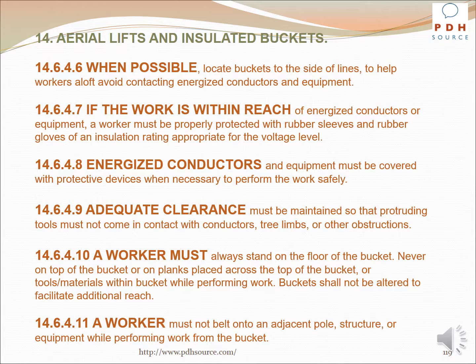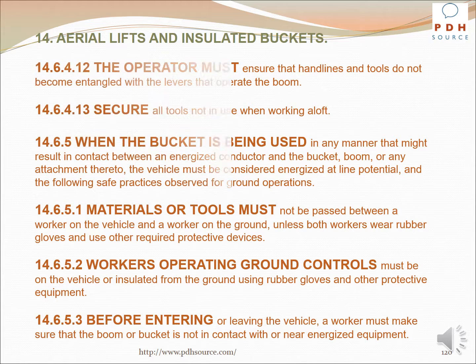Adequate clearance must be maintained so that protruding tools must not come in contact with conductors, tree limbs, or other obstructions. A worker must always stand on the floor of the bucket, never on top of the bucket or on planks placed across the top of the bucket or materials within the bucket while performing work. Buckets shall not be altered to facilitate additional reach. A worker must not belt onto an adjacent pole, structure, or equipment while performing work from the bucket. The operator must ensure that hand lines and tools do not become entangled with the levers that operate the boom. Secure all tools not in use when working aloft.